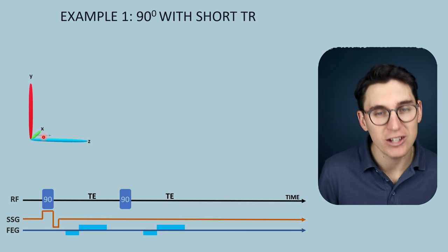The key take-home point: differing flip angles give differing signals, and using maximum flip angles in a short TR sequence is not always beneficial. Smaller angles can give better signal because the short TR doesn't allow larger flip angles to fully regain their longitudinal magnetization before being flipped again, which is responsible for the decreased signal.